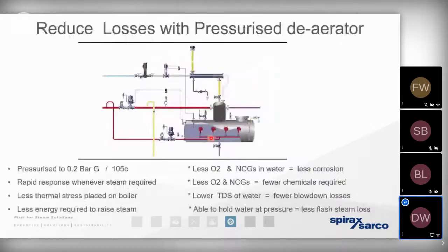We also know that moving away from a traditional atmospheric hot well towards a pressurized deaerator is going to have a number of other benefits. If we're elevating the pressure that the water is held at, we can elevate the temperature from 85 degrees in a typical atmospheric feed tank to around 105 degrees. So of course, we can generate steam far, far more rapidly whenever there's a demand. There's going to be less thermal stress placed on the boiler if we're putting hot water into it rather than slightly colder water. But it also means we've got a good head start and we need to consume far, far less fuel to raise steam again.